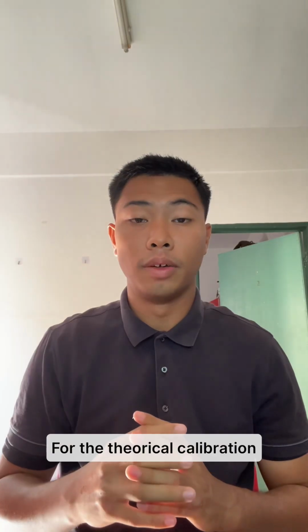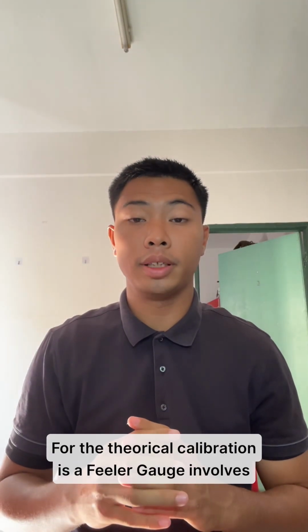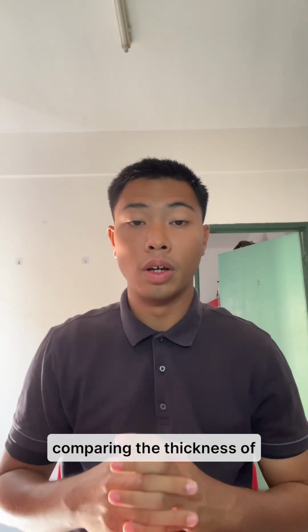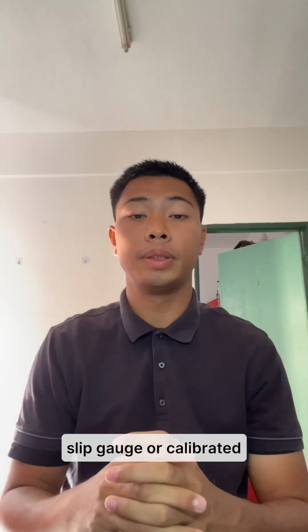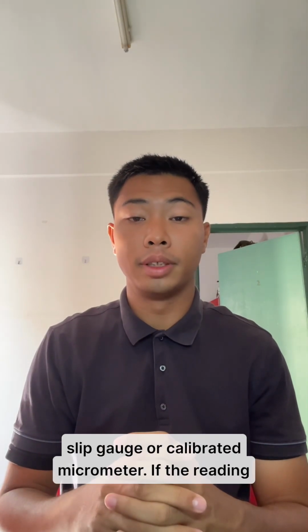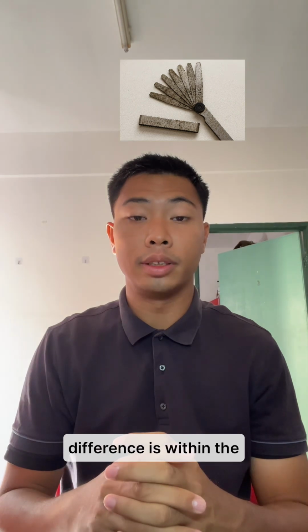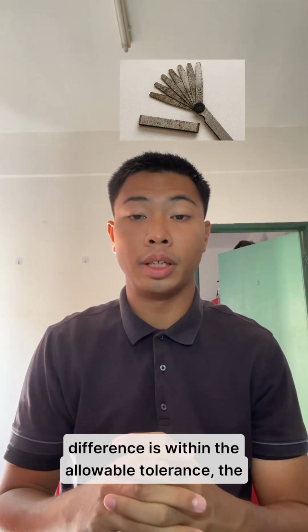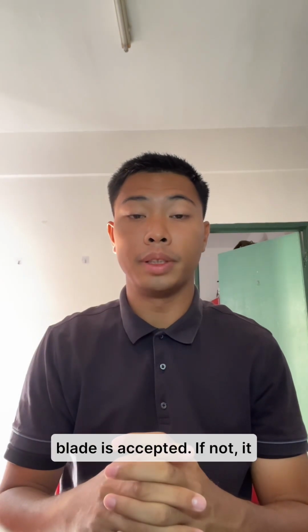The next is the theoretical calibration. Calibrating a feeler gauge involves comparing the thickness of each blade with a reference slip gauge or calibrated micrometer. If the reading difference is within allowed tolerance, the blade is accepted. If not, it must be replaced.